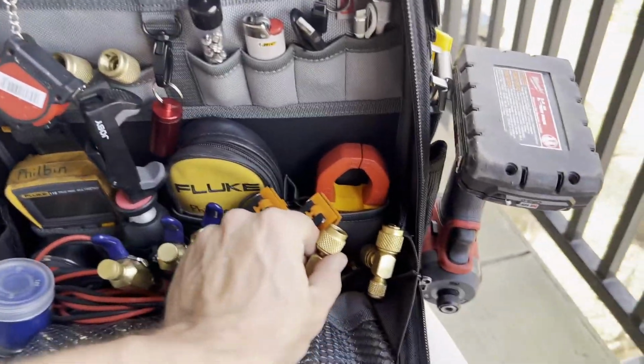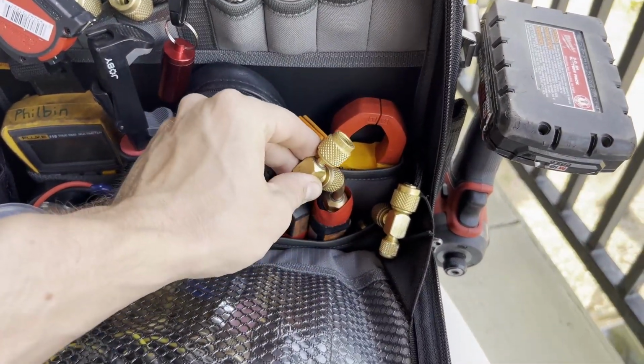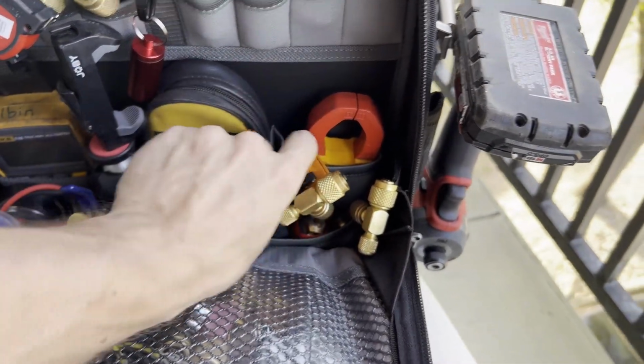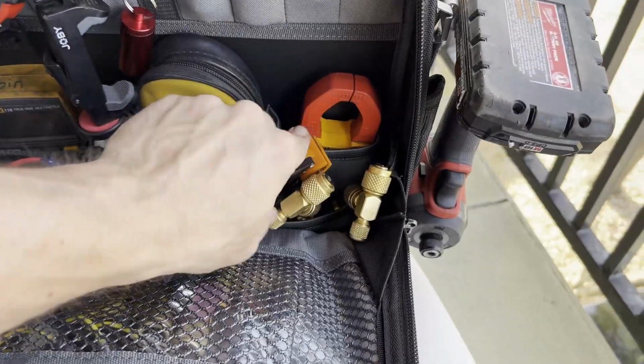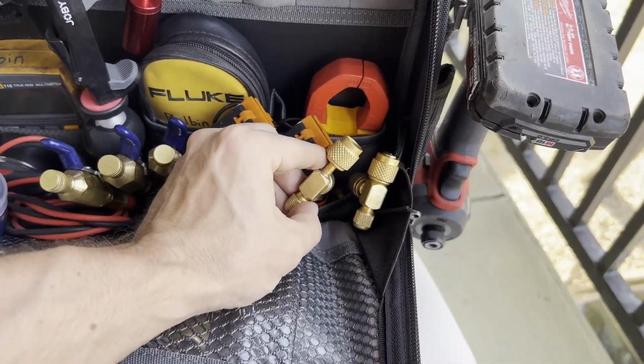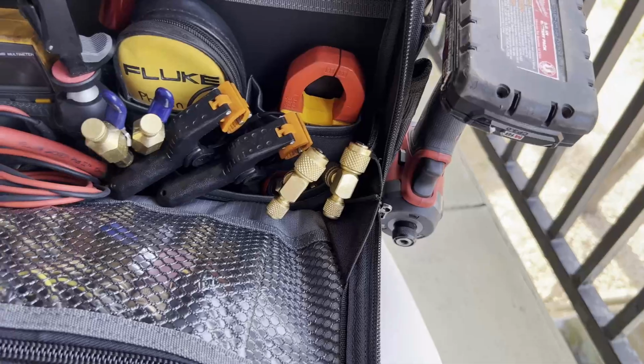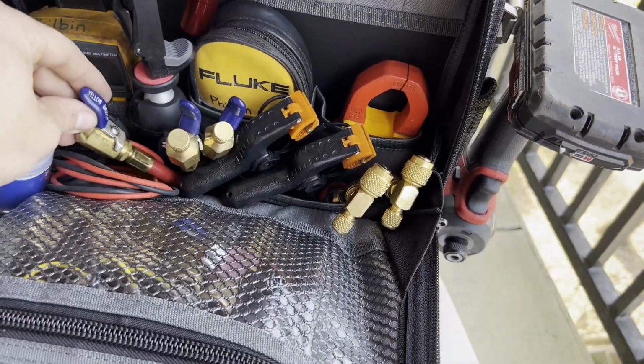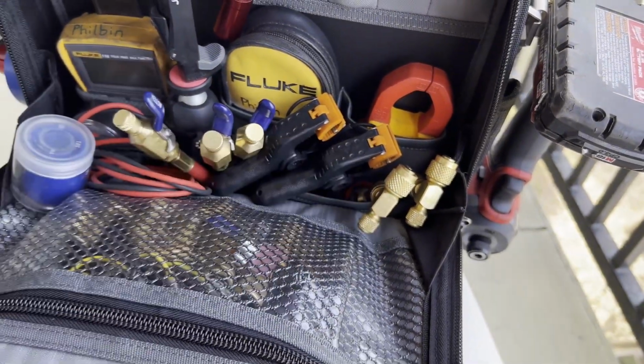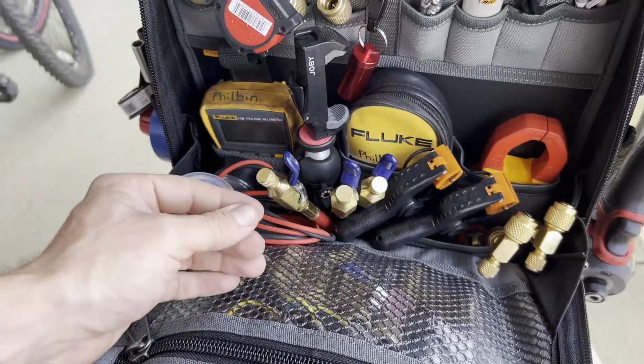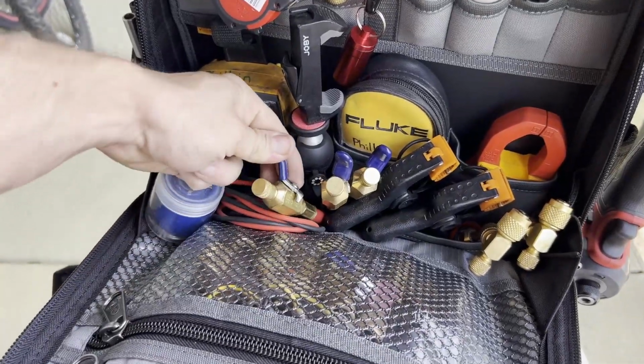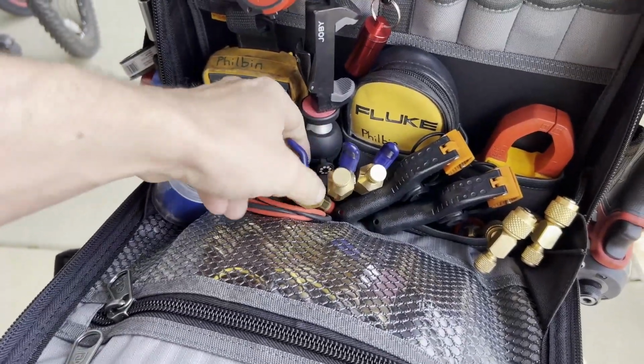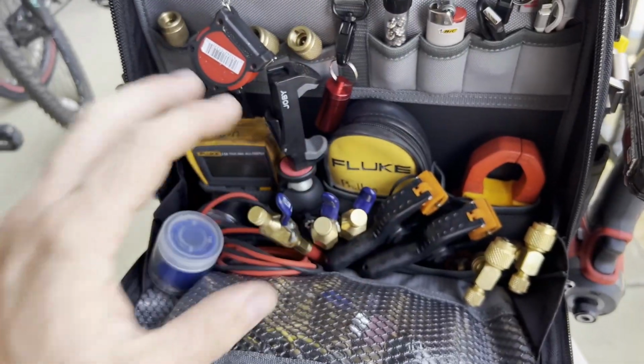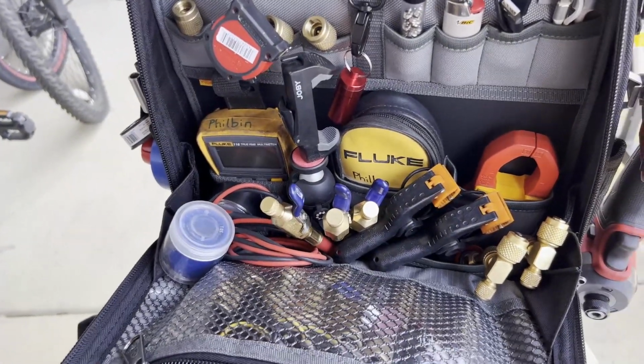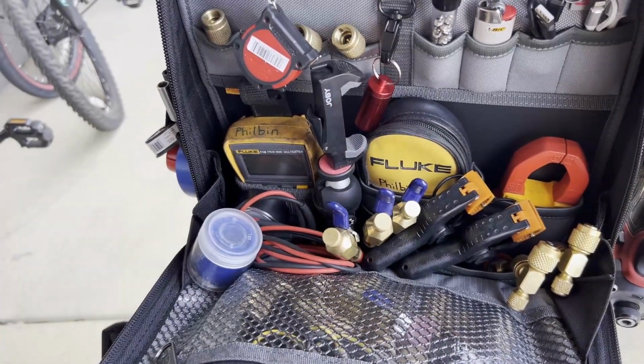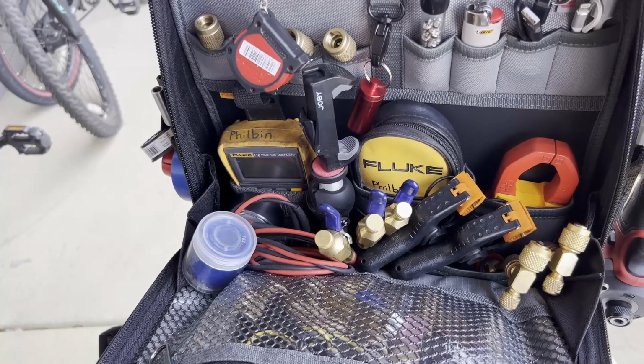To charge with my probes, I'll put these on, and I have them all labeled with red or blue for high side and low side. I'll put this on the service port, put this ball valve hose at the end right here, and then just run a hose from my refrigerant tank to this ball valve with it closed. I can purge it that way, crack it open and charge, and then I don't typically need a manifold gauge set at all. Most of the time, if I'm using a manifold gauge set, it's for pressure checking, like nitrogen or something like that.